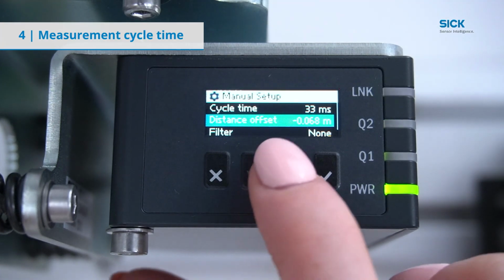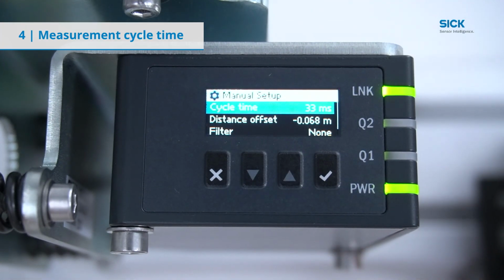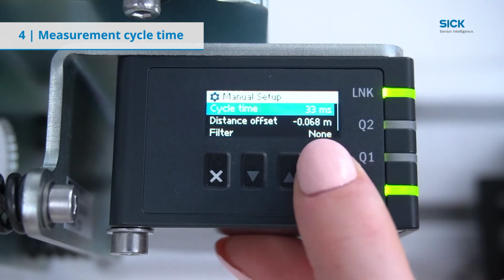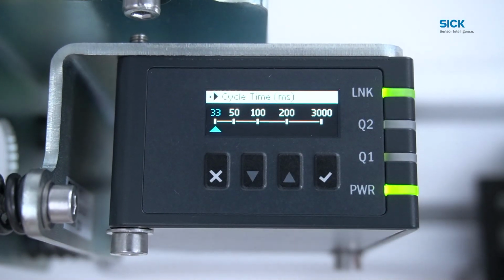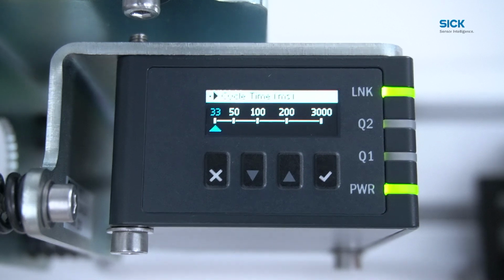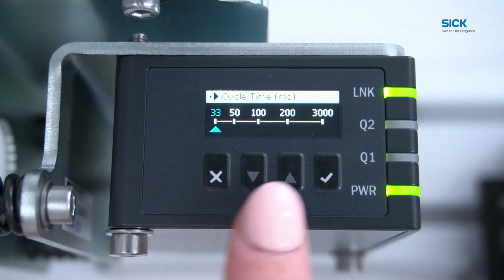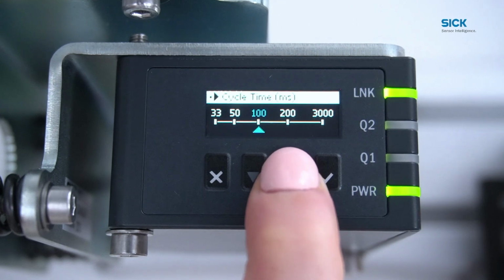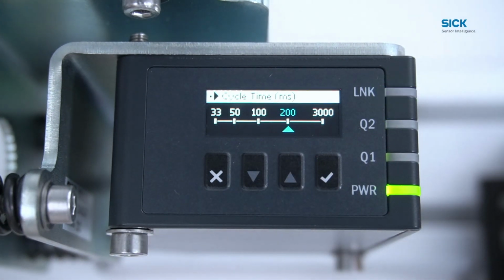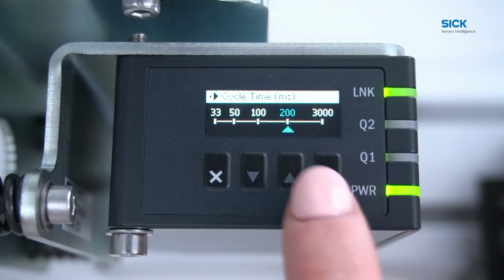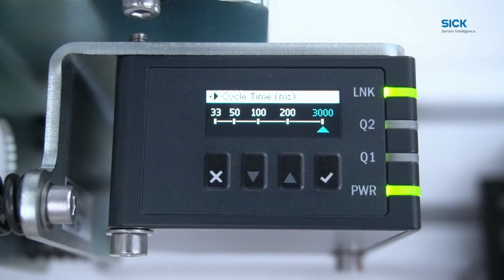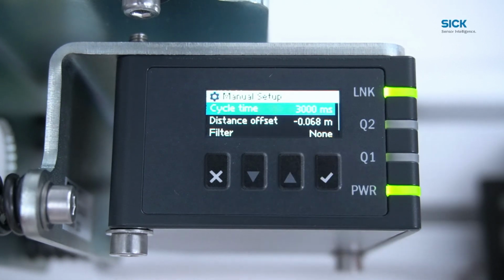The measurement cycle time defines the intervals at which measurements are performed. A shorter measurement cycle time results in a faster response time. However, this increases the signal noise. With the setting of 33 milliseconds up to 200 milliseconds, the sensor is able to measure up to 40 meters. To achieve the maximum measurement range of 80 meters, choose the setting of 3000 milliseconds. The cycle time can take up to 3000 milliseconds, but can be even lower depending on the measurement situation.